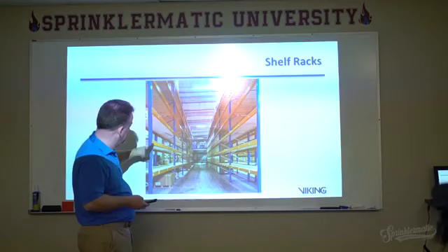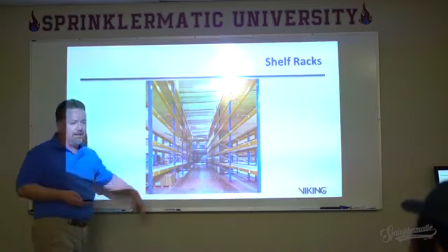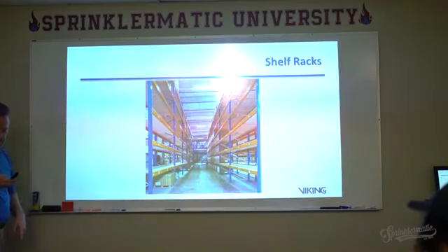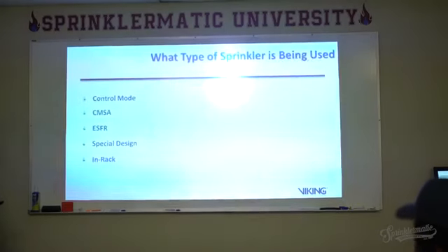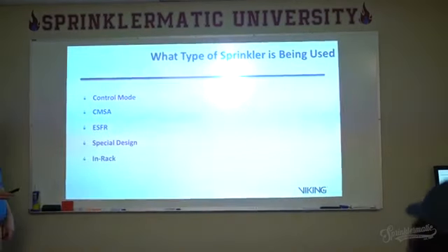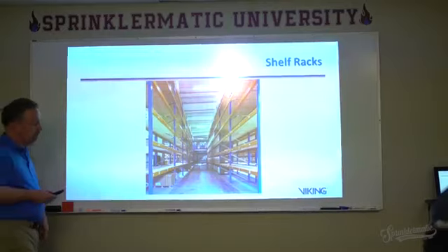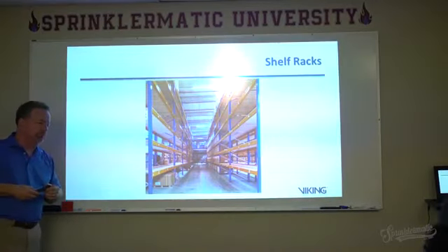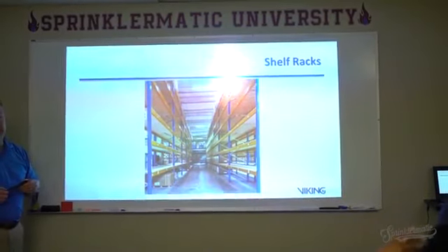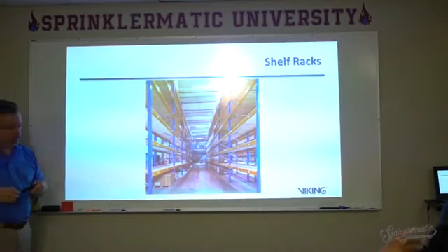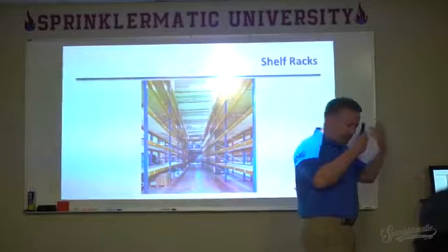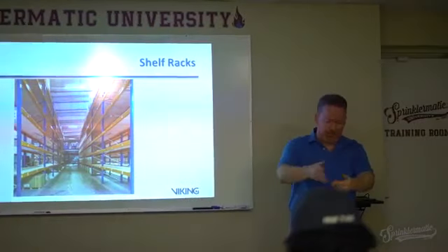What I'm not seeing right at the moment is anything down below those solid shelves. So on a company inspection, you only have sprinkler heads at the ceiling level, and they're high capacity, ESFR storage level sprinklers, one of those we're going to talk about.